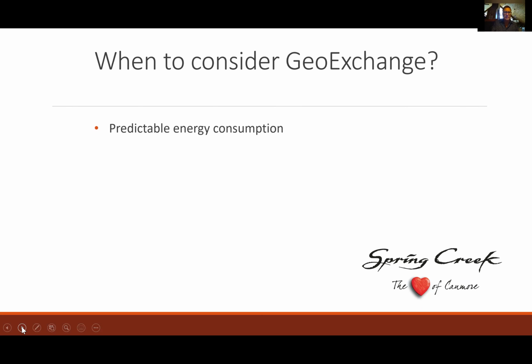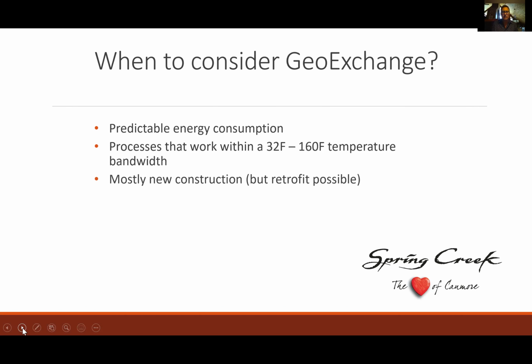But you need predictable energy consumption, you need to know how much you consume so you can size it right. That applies to any process that works between 32 degrees and 160. It used to be 110 to 120 Fahrenheit, but there are new heat pumps coming out that can work up to 160 degrees. You need around a 50 degree Fahrenheit heat sink, heat source, or field, but they are improving all the time, getting larger, more efficient, and able to work across a bigger range.